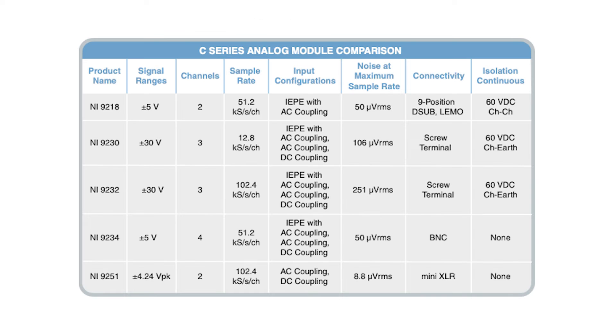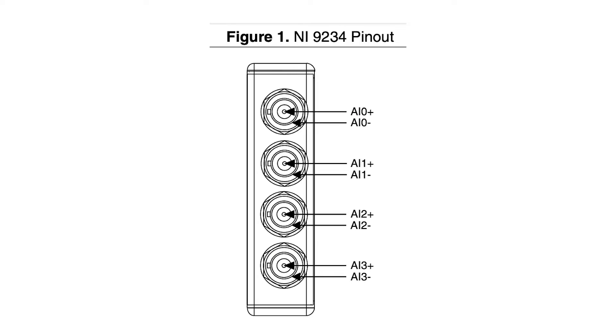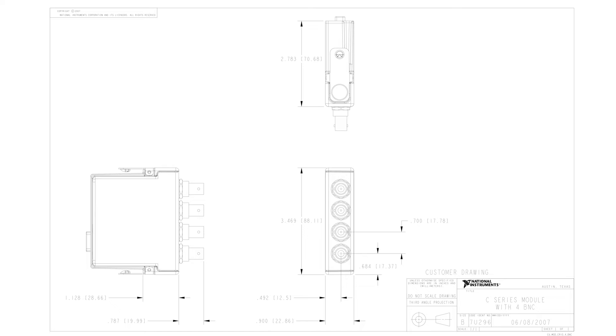The dynamic range of this module is 102 decibels. The input channels sample at rates as fast as 51.2 kilo samples per second. The NI9234 comes equipped with built-in anti-aliasing filters that have the capability of automatically regulating to the sample rate the user specifies.